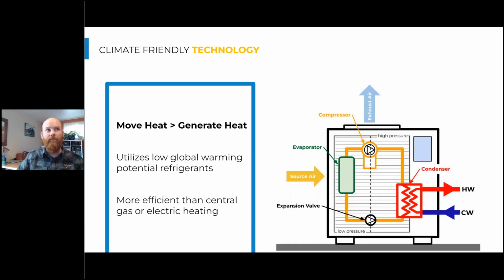So first, heat pump water heaters are really a climate-friendly technology. They're super energy efficient, and typically the refrigerants, which is the, if it leaks, is R134A or 410A, that's problematic. But the good thing about heat pump water heaters is they're confined to a small case. We have our VRF systems, variable refrigerant flow systems, for big buildings that are doing space conditioning, where you have a bunch of heat pumps on the roof and refrigerant being piped throughout the building to a bunch of fan coils in the spaces or zones. So there's a lot of refrigerant in that type of design.